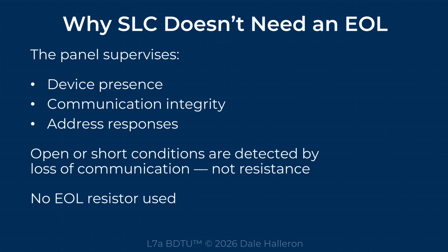Why the SLC doesn't need an EOL. The panel supervises device presence, communication integrity, and address responses. Open or short conditions are detected by loss of communication, not resistance. No EOL resistor is used.